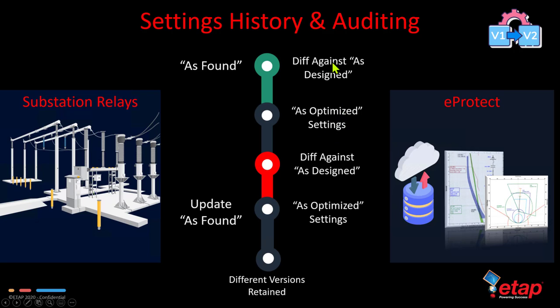So again, we can see that there are actually two versions that are kept at this stage, including the as found settings themselves. Another version can be created where you're doing a diff against the as designed versus optimized. For those of you who use ETAP would know that the as designed is usually kept in base revision and as optimized could be kept in another revision. And we're essentially doing a difference against the base versus revision versus the settings that are being retrieved from the eProtect database. You can then create an as optimized setting file, which is then created based on the optimized settings that are merged into base.